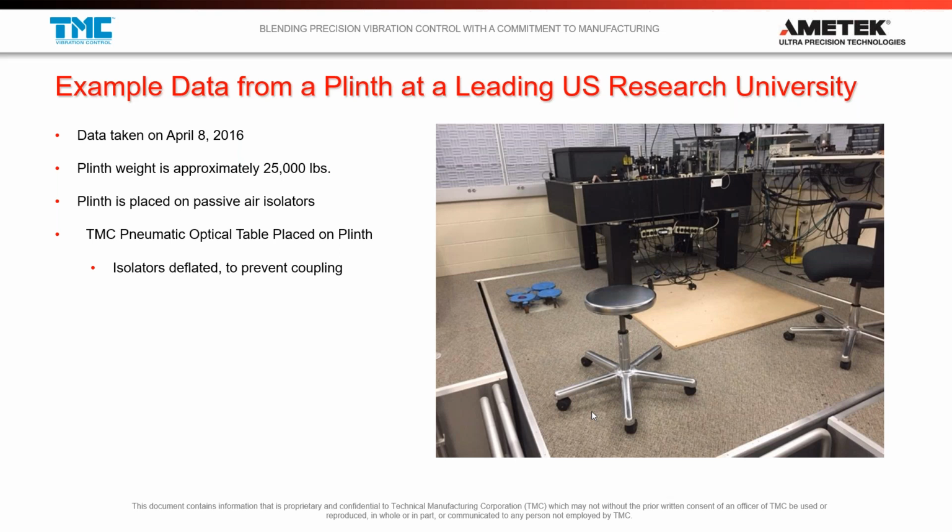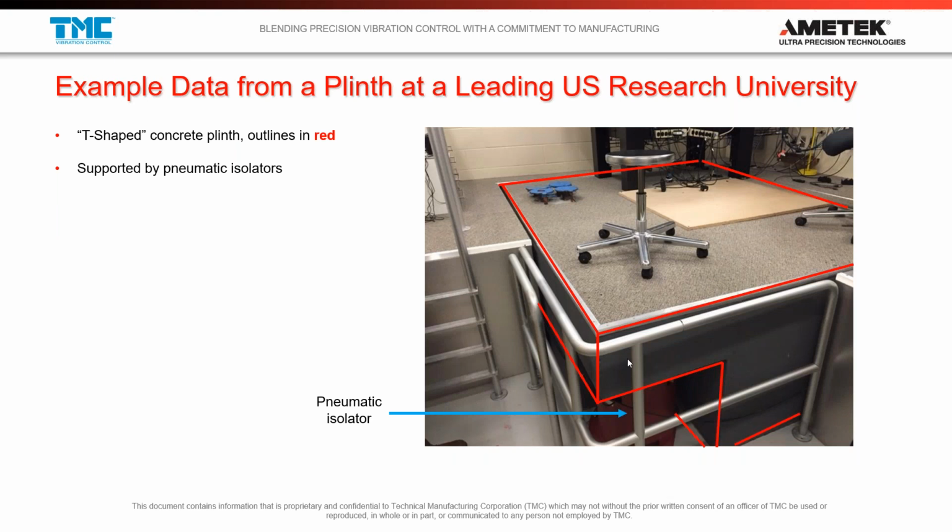Okay, so let's talk a little bit more about stacking systems. And here's a really cool example. Here's a plinth at a leading US research university. What we have here is an optical table placed on this isolated plinth. I'll go here to show a better photo of the plinth. It's a classic T-shaped plinth, weighs about 25,000 pounds, and is supported by pneumatic isolators.